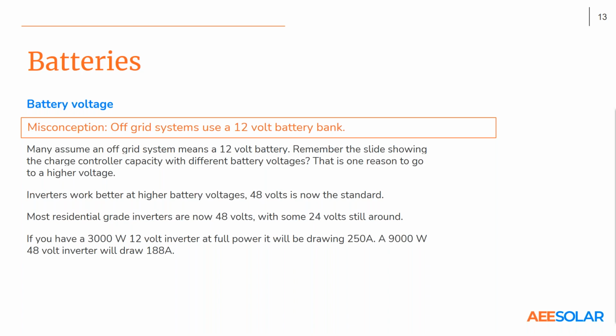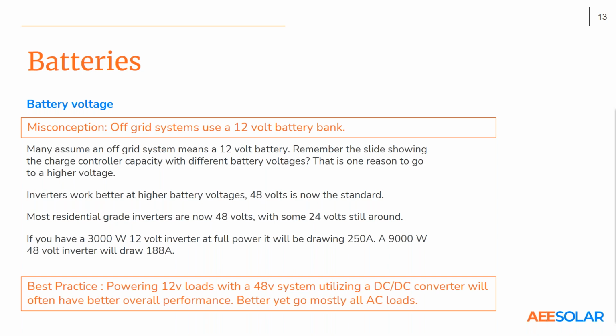And just to give an example, if you've got a 3,000 watt 12-volt inverter at full power, it's going to be drawing 250 amps. If you have just a single string of lead batteries, your standard 100 amp hour or 200 amp hour battery with the lead posts on it, 250 amps is enough to almost melt those posts. And if you start pulling some surge power out of it, you're going to have some pretty serious issues with your battery bank being overheated. On the other hand, a 9,000 watt 48 volt inverter is only drawing 188 amps, and that's 3 times the size and drawing less current. So it really pays to use a higher voltage battery bank.